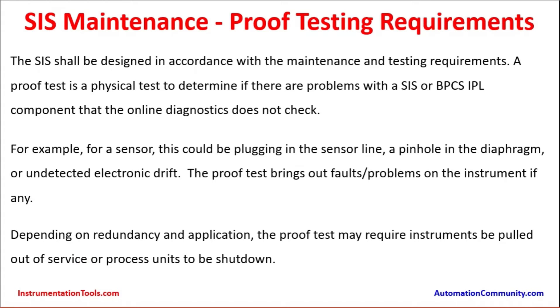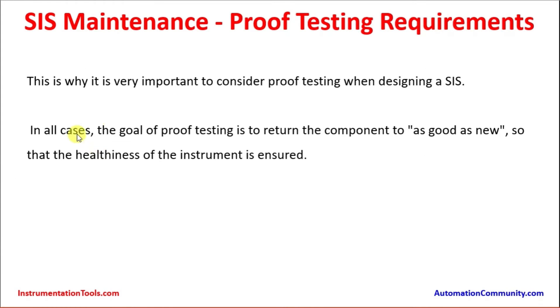Depending on redundancy and application, the proof test may require some instruments to be pulled out of service or the process to be shut down. If there is a 1oo1 configuration and proof testing cannot be done online, it may call for shutdown of a part of the plant or equipment. This is why it is very important to consider proof testing when designing a Safety Instrumented System. The goal of proof testing is to return the component to 'as good as new' condition, resetting it for the next calculated interval.